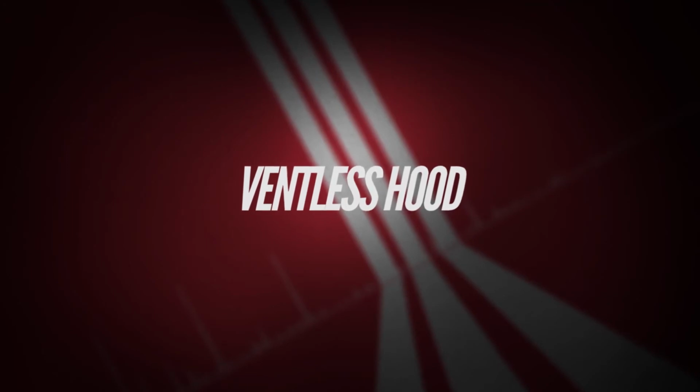Next, ventless hoods. These come in both countertop and canopy style, and instead of venting out of the building, they're actually using air scrubbers and cleaners to clean and recirculate the air back into the space. These hoods, however, do not remove heat from the area.